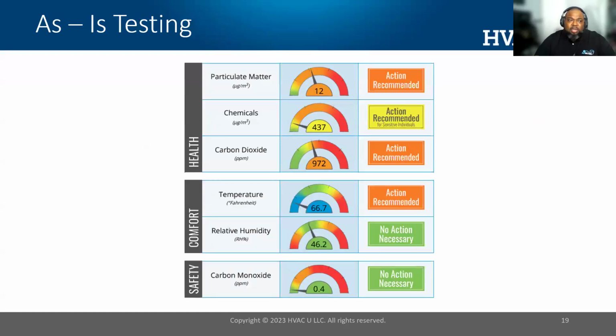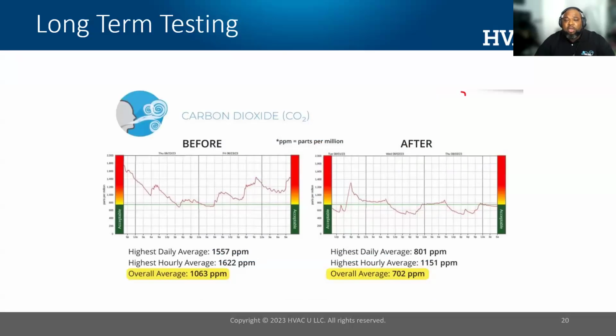All right. Again, this is as-is testing. It gives you raw data, with no context in it. And this is long term. So this is actually a project that I fixed where the customer was experiencing high levels of carbon dioxide. After we implemented an ERV, similar to the products that Brett mentioned earlier, we were able to bring that carbon dioxide level down. And as a result, we were able to track and get instant confirmation that our IAQ strategy actually worked. So this is a long-term test. This was deployed over a couple of days to actually verify that the levels were coming down.